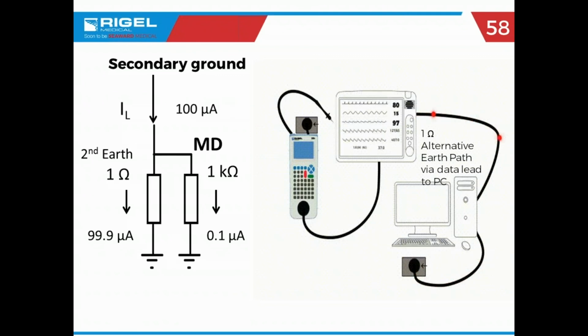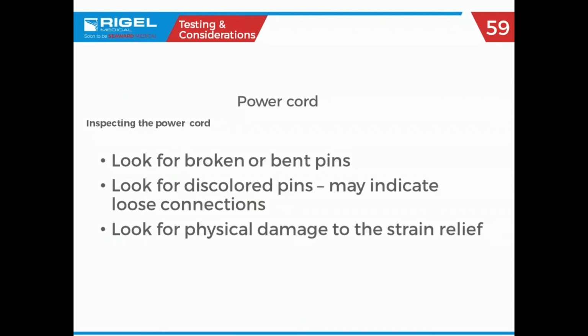The products that you see up here will come up because it expects to see something. They'll give you a warning message. It says, check for secondary ground. So it ensures that you're not fooled. Because if there was greater than 500 microamps and there was that secondary ground, you look at it, you're going to see a couple of microamps, you're going to go, we're good. But no, because if that secondary ground was ever disconnected in the procedure room, you have the capability of having leakage current. Bada bada boom. So power cords, look for broken or bent pins, all kinds of, this is just logic.